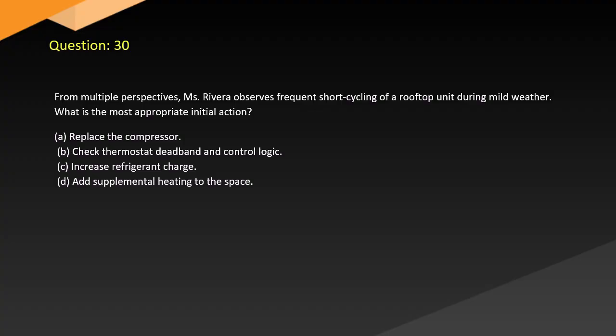Question 30. From multiple perspectives, Rivera observes frequent short cycling of a rooftop unit during mild weather. What is the most appropriate initial action? A. Replace the compressor. B. Check thermostat deadband and control logic. C. Increase refrigerant charge. D. Add supplemental heating to the space.